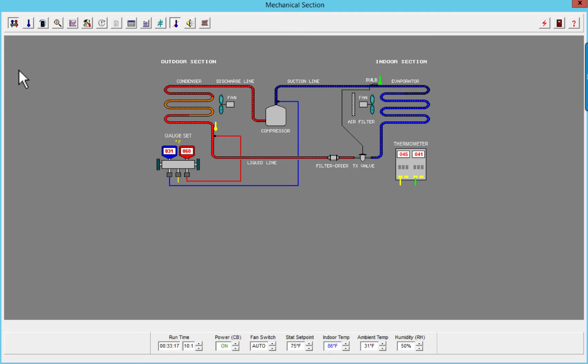So what we can do is wrap a tarp around the unit, and in this case, we're going to block the coil a little bit. Watch what happens when I do a 50% block of that coil. What is going on with my temperatures? All of a sudden, regardless of outside air temperatures, you will see immediately that my pressures have changed. My coil temperature is now above 32 degrees. We're at 36 degrees.